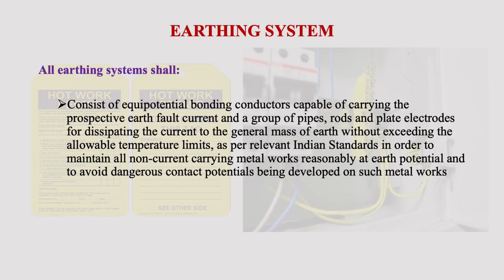The first: it must consist of equipotential bonding conductors capable of carrying the prospective earth fault current, and a group of pipes, rods and plate electrodes for dissipating the current to the general mass of the earth without exceeding the allowable temperature limits. As per the relevant Indian standard, this is to maintain all non-current carrying metal works reasonably at earth potential, and to avoid dangerous contact potentials being developed on such metal works.